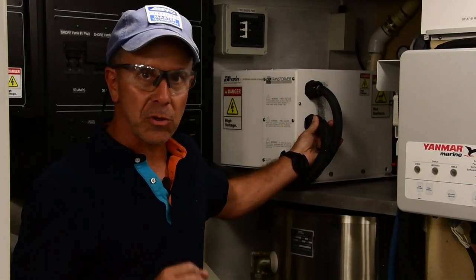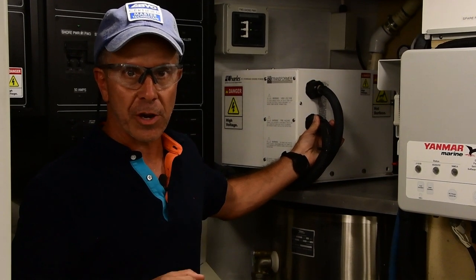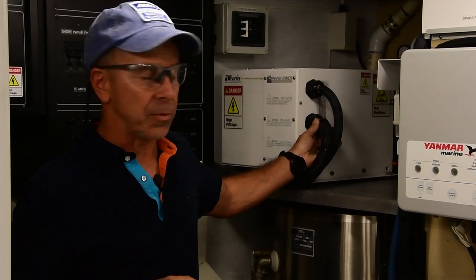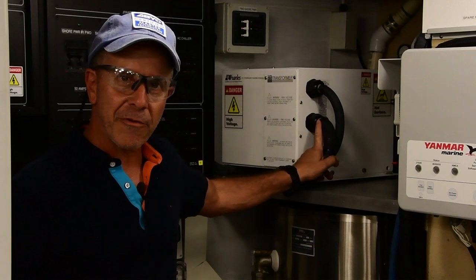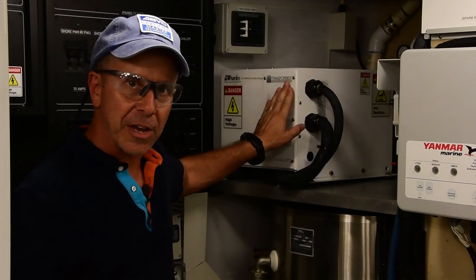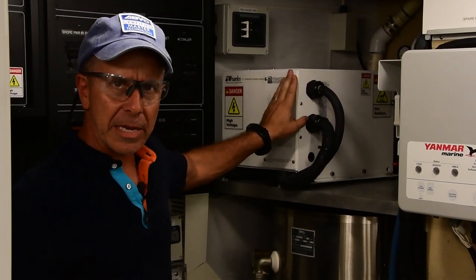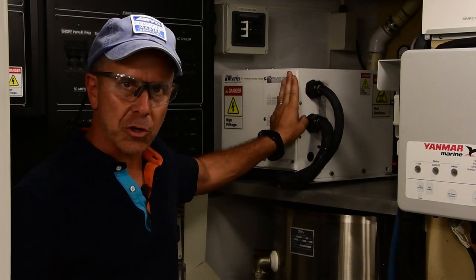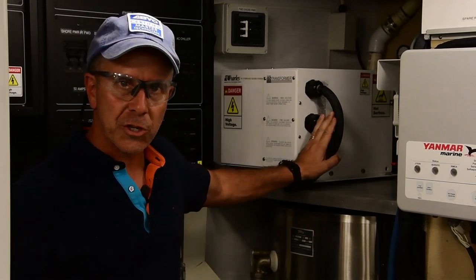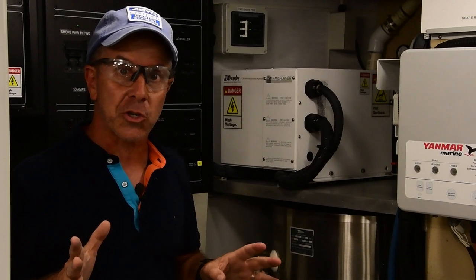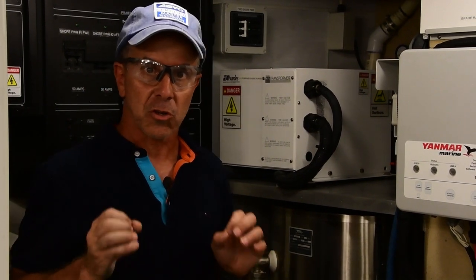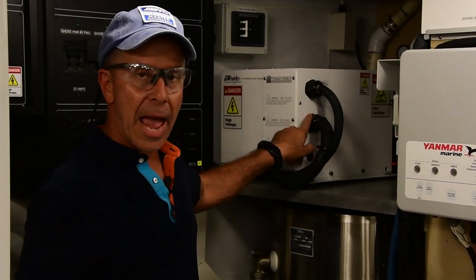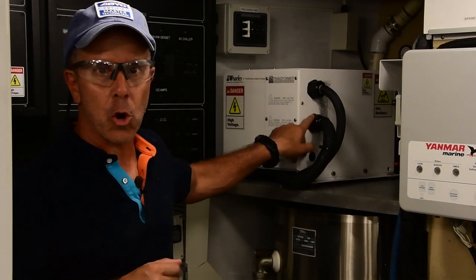That is absolutely essential for any transformer installation. What does that do? The cord grip prevents wires from chafing against the enclosure, the metallic enclosure of the transformer. If a wire chafes against that enclosure, it could potentially be an electrocution hazard. So it's critically important that that cannot happen.